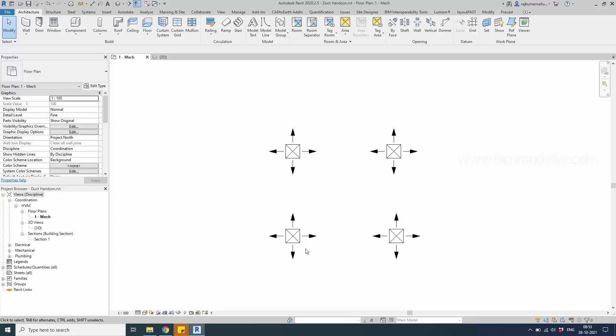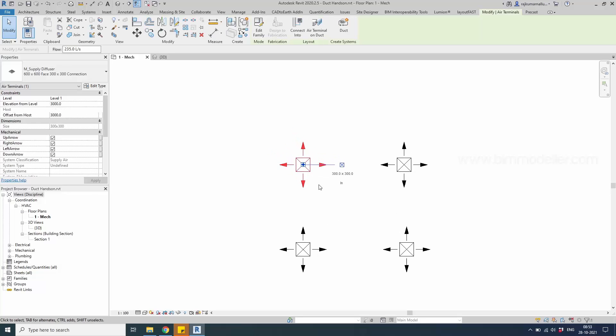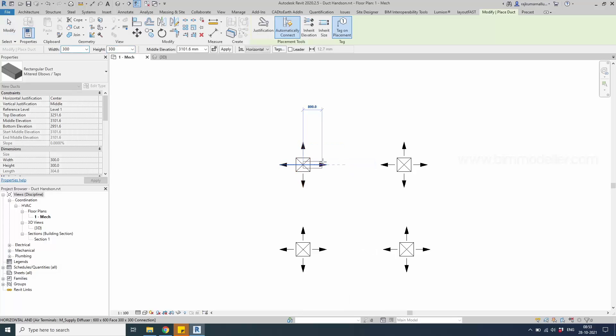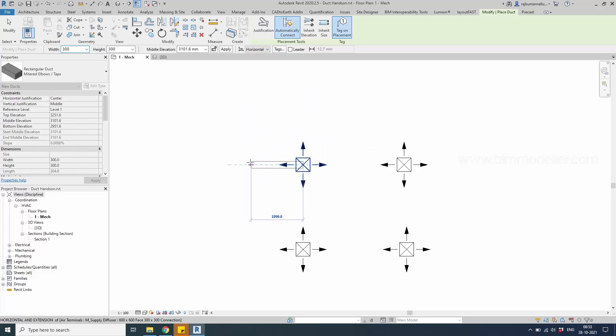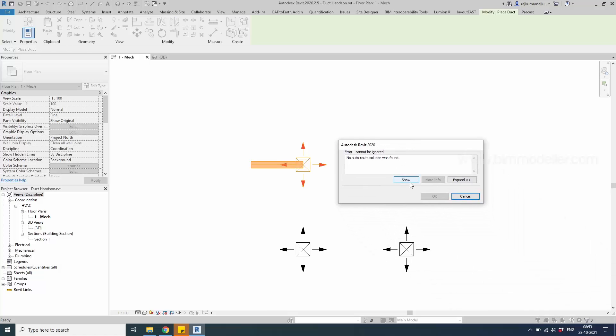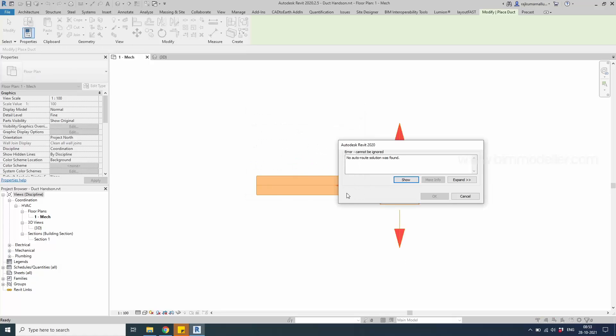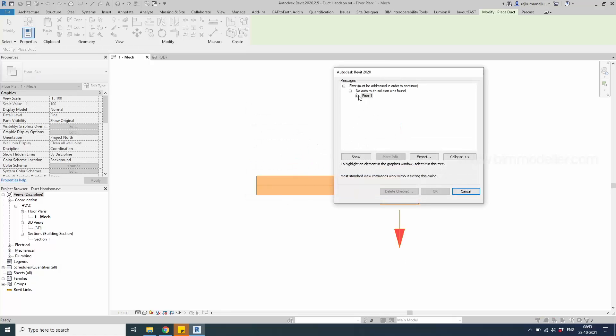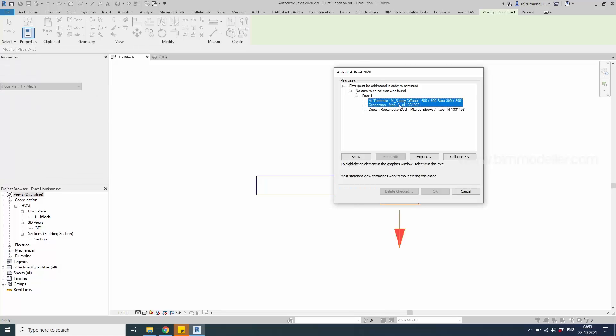Hello everyone, welcome to BIMODELER. This is a short tutorial on how to avoid the 'no auto route solution' error. If you are starting a new project as a beginner, you will place an air terminal and then try to create a duct connection by right-clicking and drawing it in some direction.